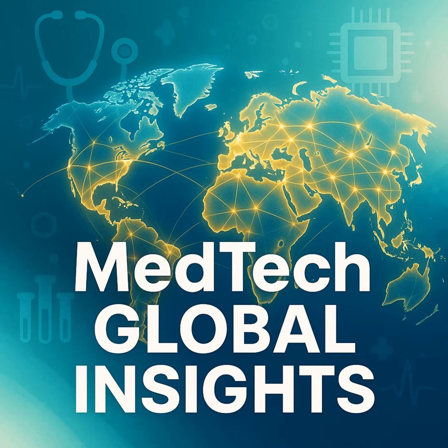This brings us to the technical documentation, which is where many innovators face significant hurdles. Regulators need to see far beyond your final output. You must meticulously document the entire life cycle of your algorithm. This includes the sourcing, labeling, and management of the datasets used for training, validation, and testing. It is crucial to prove that your data is unbiased and truly representative of your target patient population in Europe.